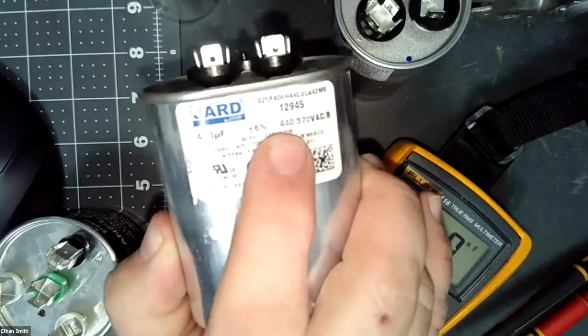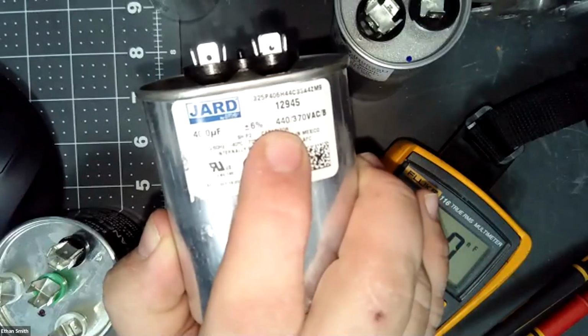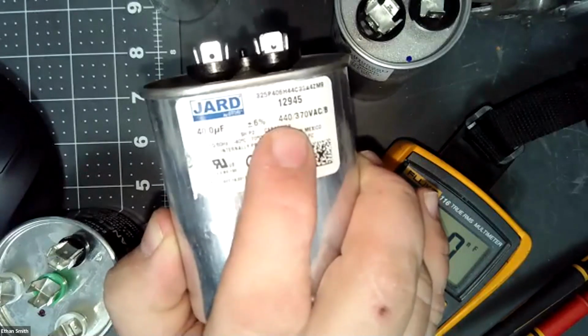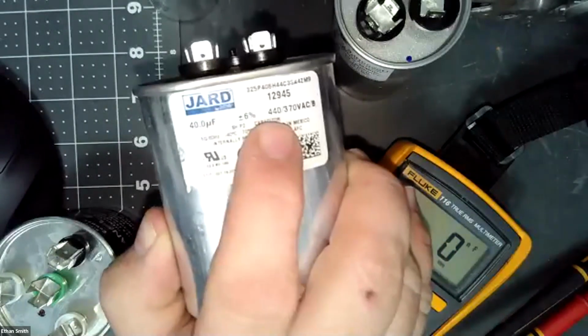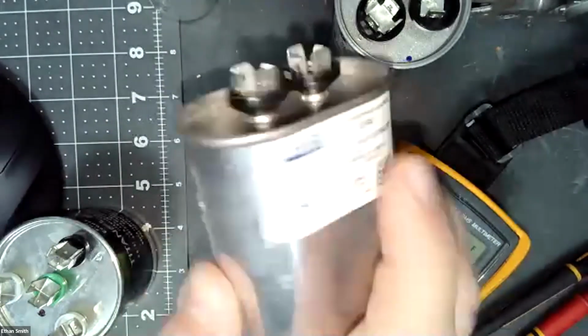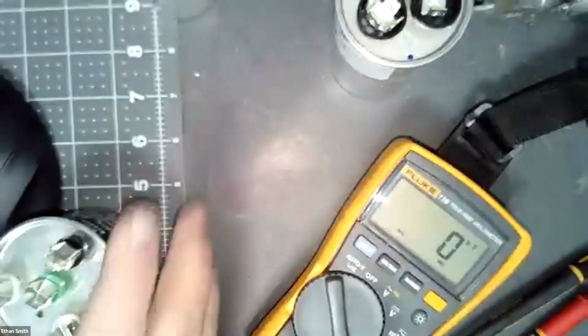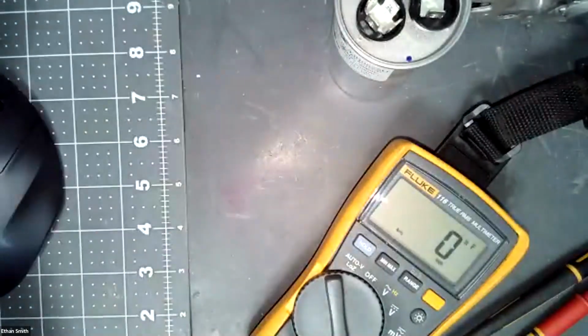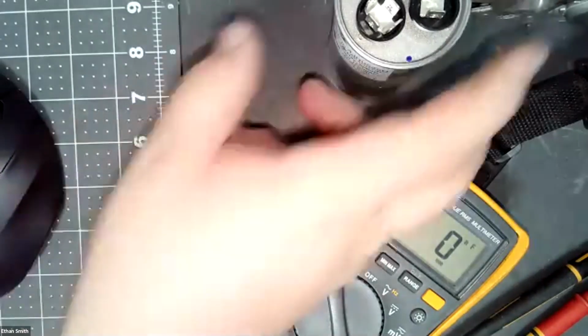It refers to the insulation value. So we can always have extra insulation. That's not a problem. But if we don't have enough insulation, it will result in a premature failure of the capacitor and probably the motor as well. So any questions about capacitors, guys?